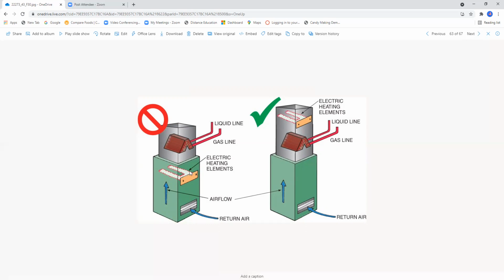When I installed this heat pump project in Port Orchard, Washington this summer, the evaporator coil was located down here, and a strip heat package was located up here along with the fan, which is fine because it was a downflow application. So notice that the correct installation shows the electric strip heat elements above the evaporator coil, or the indoor coil in this case.